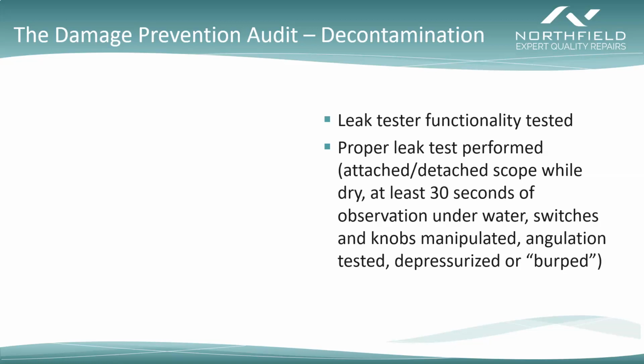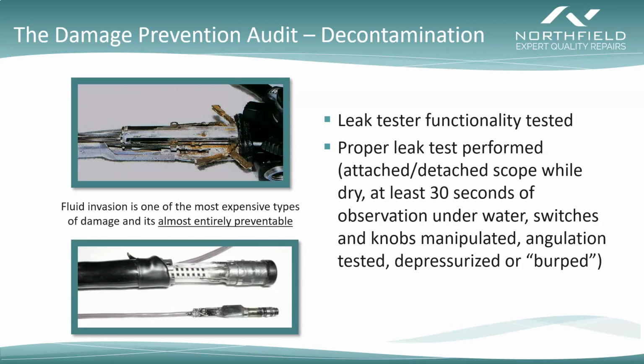And after we're done with that leak test, we want to make sure that we depressurize or burp that scope. Leak testing is so critical from a cost-saving standpoint because fluid invasion really is one of the most expensive types of damage, and it's almost entirely preventable. You can see from these pictures some of the damage that's done by fluid, and you can see corrosion. The bottom picture has the CCD chip that was completely destroyed by fluid, and the result of that is a lot of expensive damage to that device, and it takes a really long time to get repaired.